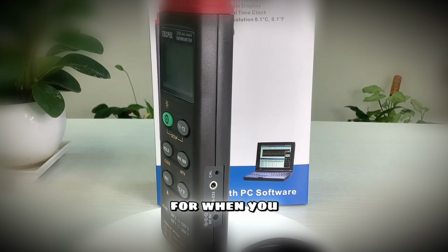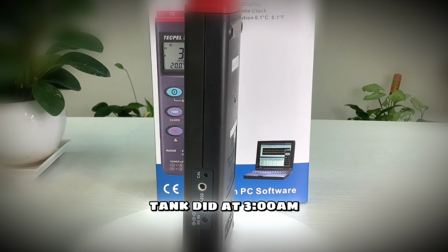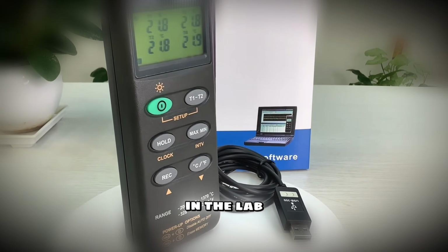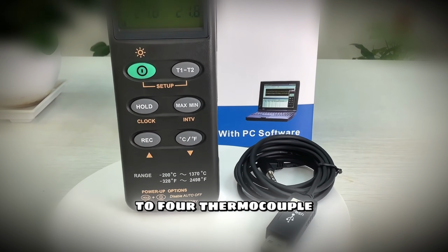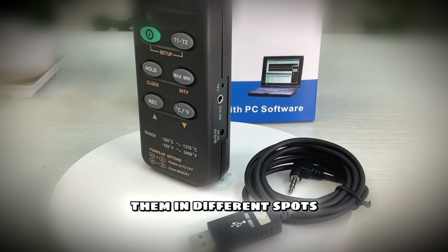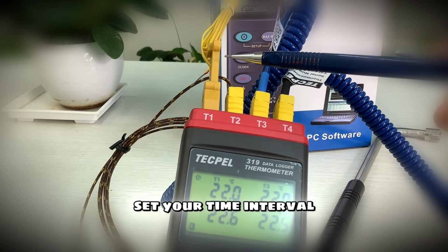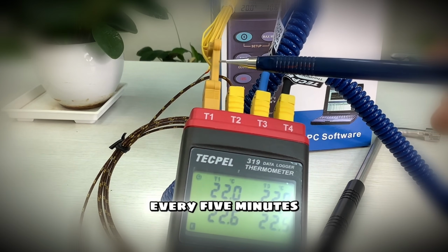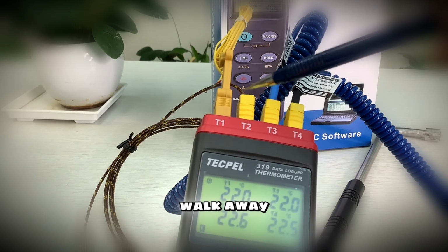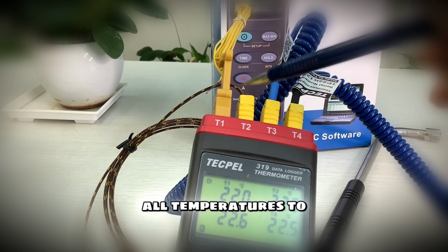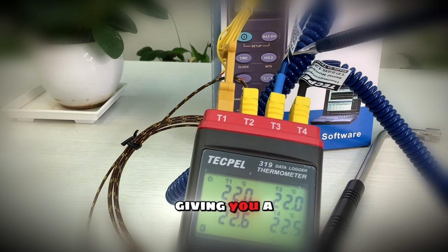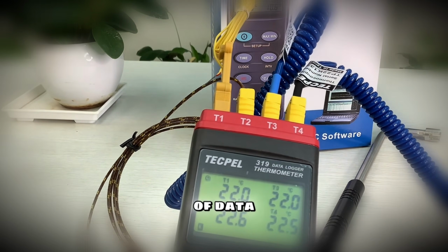Our third tool eliminates human error and handles long-term monitoring, the 4-channel data logging thermometer. It is perfect for when you need to know exactly what a curing tank did at 3 a.m. when nobody was in the lab. How to use it? Plug in up to 4 thermocouple probes and place them in different spots. Turn it on, set your time interval, like 1 reading every 5 minutes, and press record. You can just walk away. It automatically logs all temperatures to an SD card, giving you a flawless, unalterable spreadsheet of data.